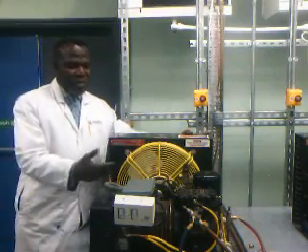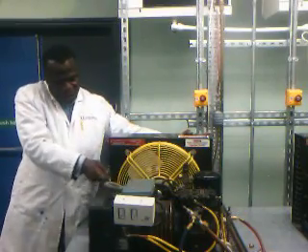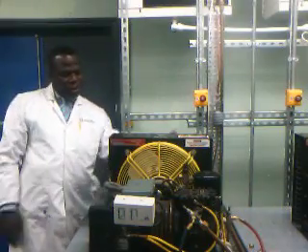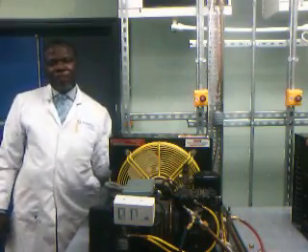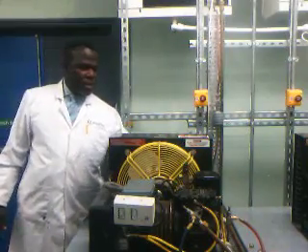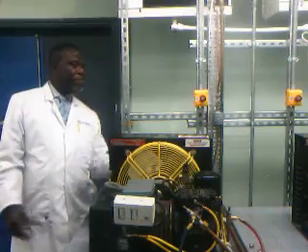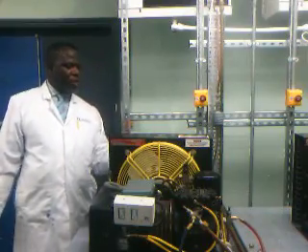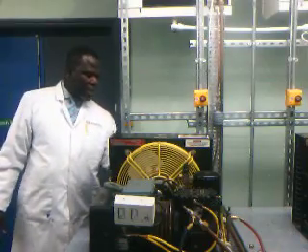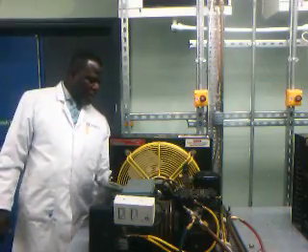Refrigerant will lose sensible heat on the discharge line. Throughout the first and second lines of the condenser, you have what we call desuperheating, which is the reverse of superheating. The superheated gas loses a bit of heat, but it continues to change state, so you have a mixture of liquid and vapor in the condenser, especially in the middle of the condenser.